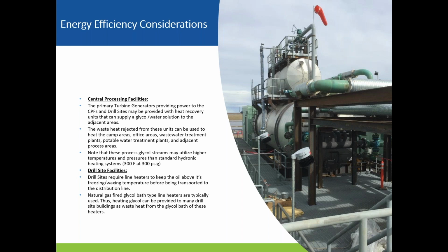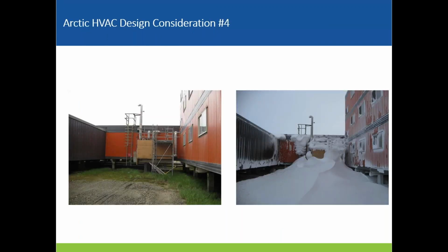One thing I'll note with the HRUs, at least at our facilities, that heating glycol is coming off at a higher pressure and temperature than standard commercial system. That always becomes a problem during your design phase. Special coils, special valves, class 300 system.